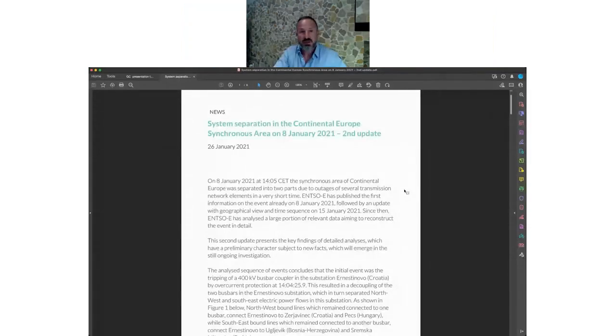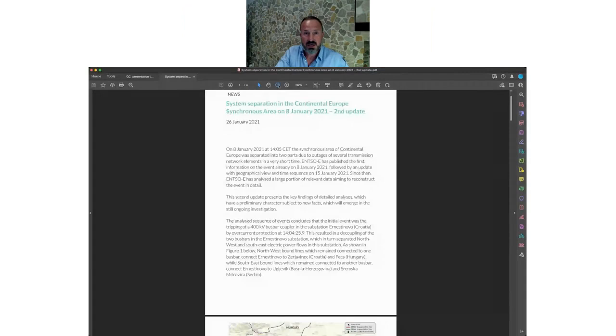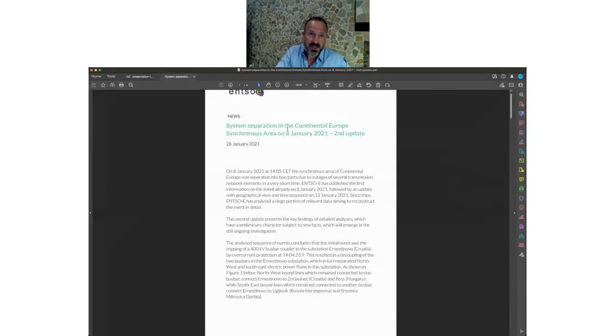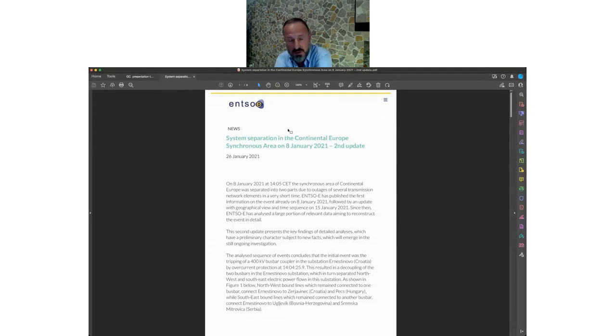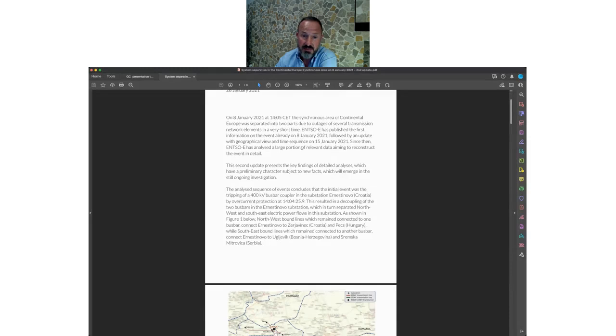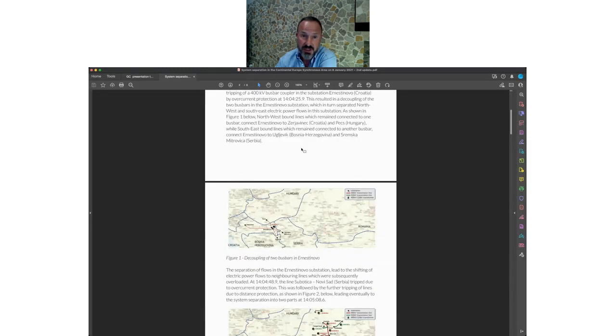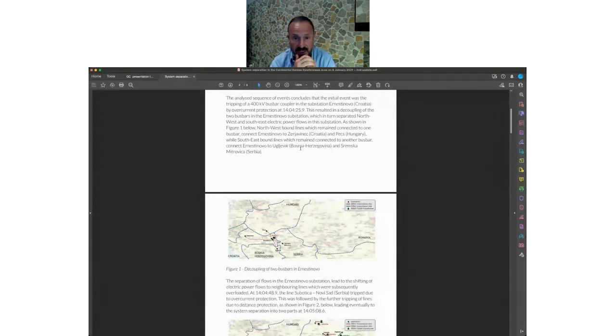I'm sharing this document because it's an interesting document published by ENTSO-E, the Association of Transmission System Operators of Europe. Following the event, since it was serious, there was an investigation. The investigation analyzed the sequence that happened on the 8th of January 2021 at 14:04, starting from an anonymous substation in Croatia that, for a very silly reason, had the decoupling of two bus bars.